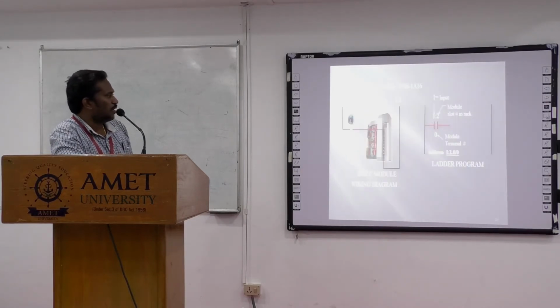This is a simple example of wiring connection between your PLC and the input device, and the right side one is the ladder diagram. For the input, we have to create a ladder diagram. The ladder diagram input is indicated by a contact, an NO contact. Here we have connected our NO switch, so that will be represented by an NO contact in the ladder diagram program. We have to enter the address in the ladder diagram, then only the PLC will understand the input which is connected to the terminal.